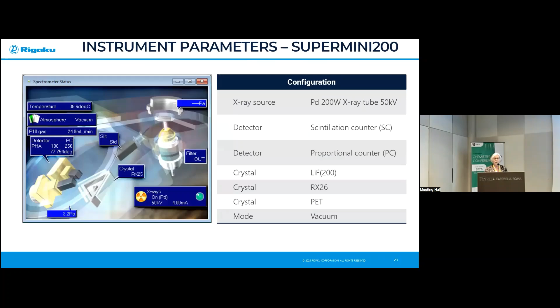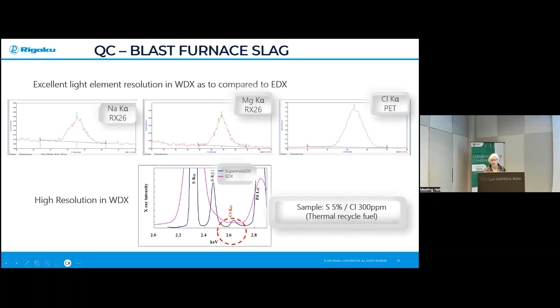So of course, as you can see, we have excellent light element determination for elements like sodium, which are very difficult in X-ray fluorescence, magnesium and chloride, as compared to smaller kind of units. So if you look at this diagram at the bottom here, you will see the spectral energy profile for energy dispersive instrument where we cannot pick up chlorine, but with our Rigaku Super Mini, we can pick up even 300 parts per million of chlorine in a very difficult matrix.